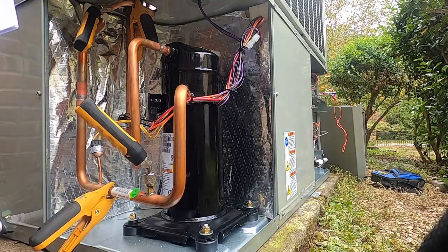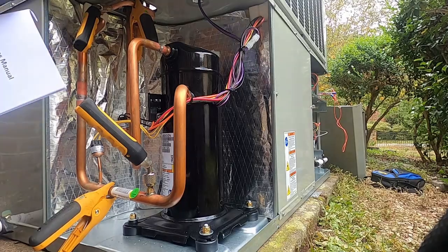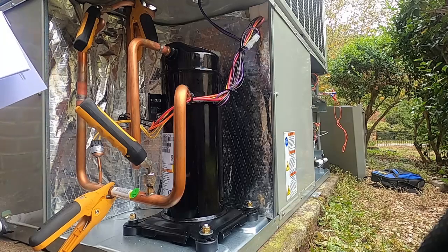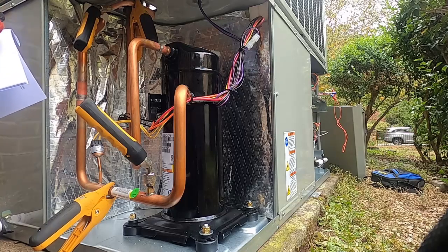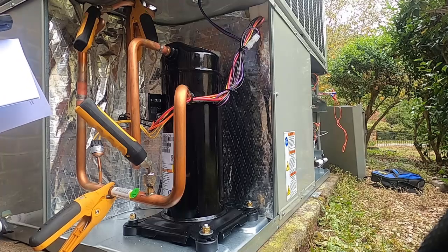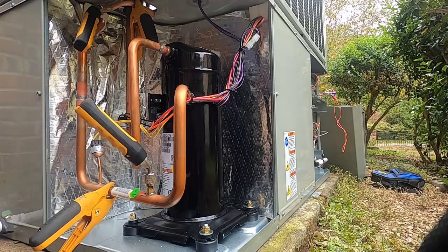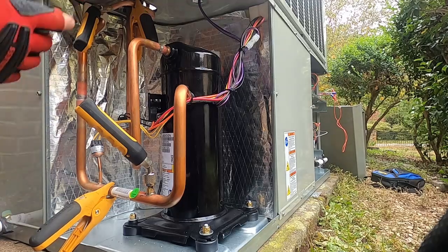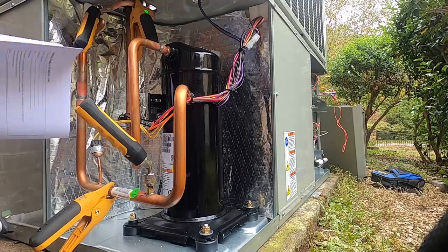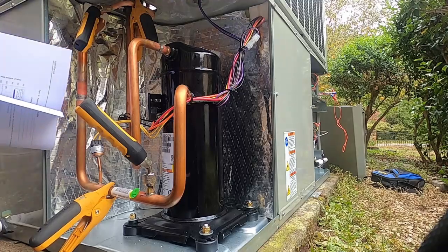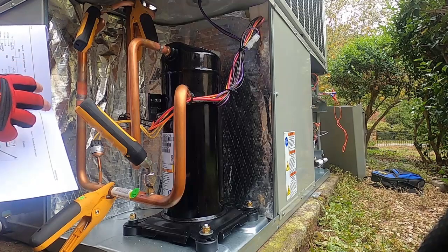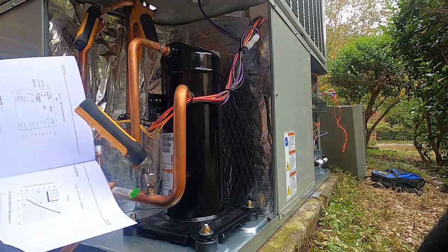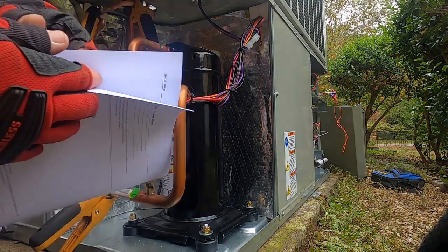Alrighty, so we've got this thing running and cooling. Got the book here. I'm going to compare some things. I've checked the static on it. We're right at a 0.5 static on this. There's no subcooling. Typically the outdoor units will give you a target subcooling. This one doesn't. Some of the units would sometimes put it in a little box here in the book. This one just gives you pressure curves.